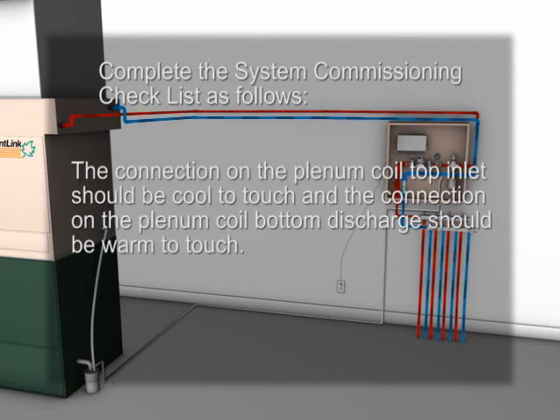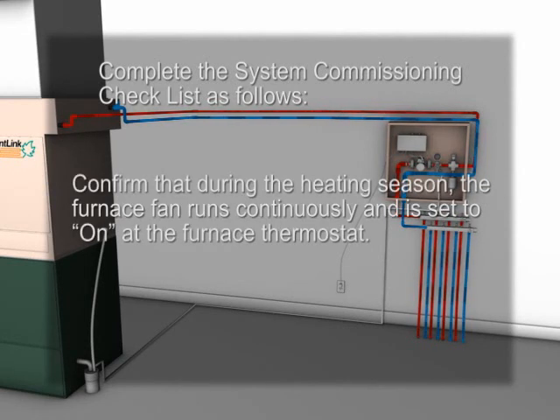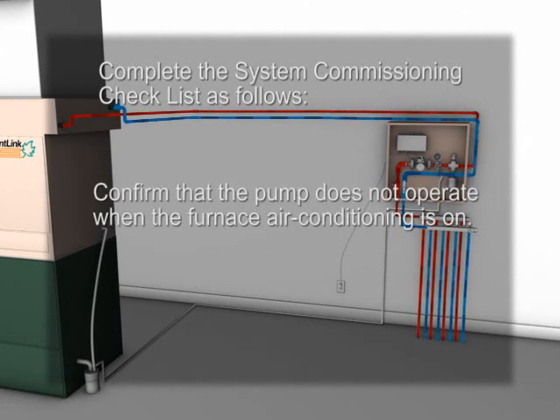The connection on the plenum coil top inlet should be cool to touch, and the connection on the plenum coil bottom discharge should be warm to touch. Confirm that during the heating season, the furnace fan runs continuously and is set to on at the furnace thermostat. Confirm that the pump does not operate when the furnace air conditioning is on.